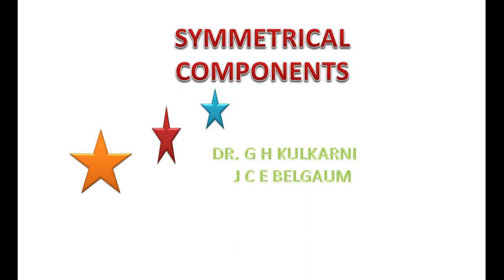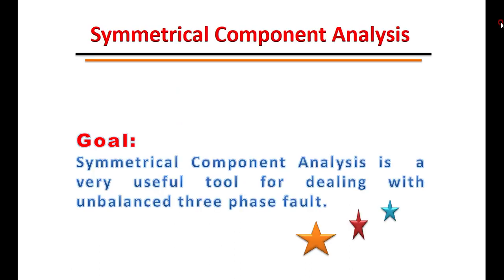We will study how the symmetrical component method is applied to unbalanced faults. The goal of symmetrical component analysis is that it is a very useful tool for dealing with unbalanced three-phase faults. In the case of a balanced fault, all phase currents — Ia, Ib, Ic — have equal magnitude and a phase angle of 120 degrees with each other, and such problems can be tackled by analyzing on a per-phase basis.